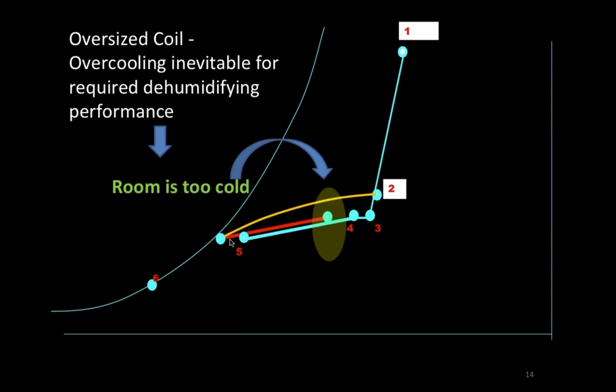But because we can't use active reheating in most designs, in Singapore we are not allowed to use active reheating for comfort air conditioning, we tend to leave that condition cold. The consequence is the humidity is right, perhaps, but the space is cold. So you've got the choice. You've got to pick what you want to have in terms of room condition. Something that's right in terms of temperature, but more humid, or it's correct in terms of humidity, but cold. So it's cold or humid.